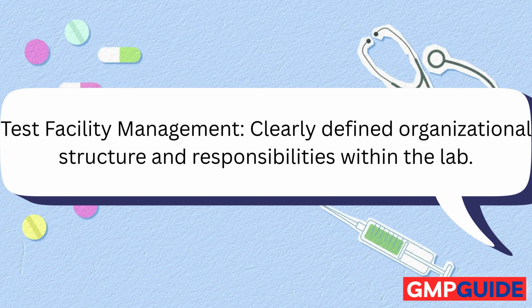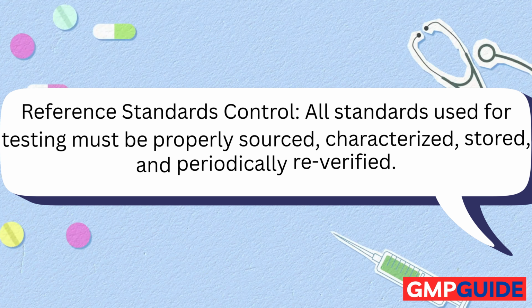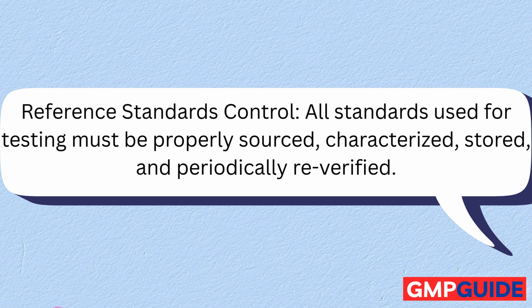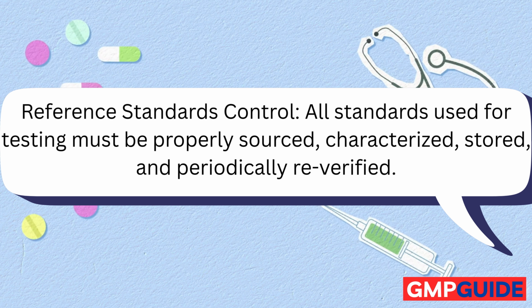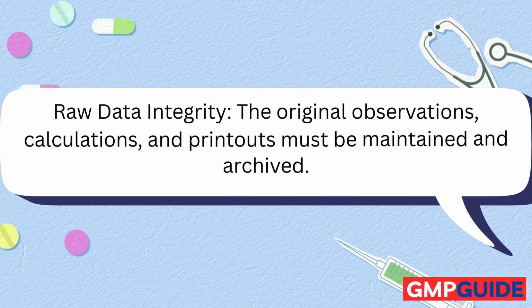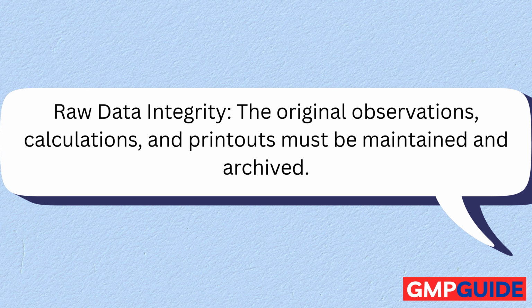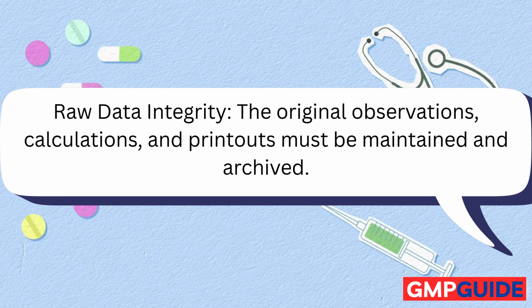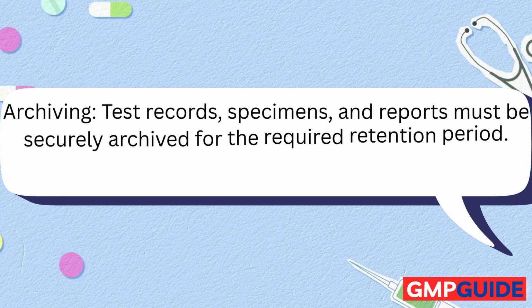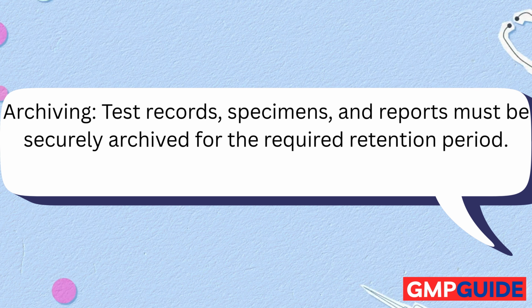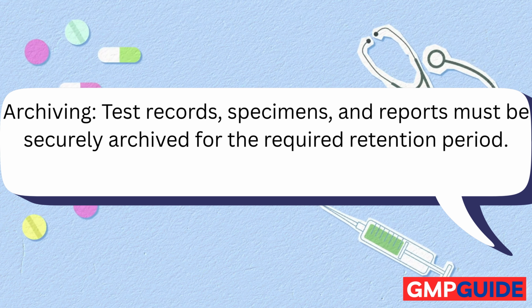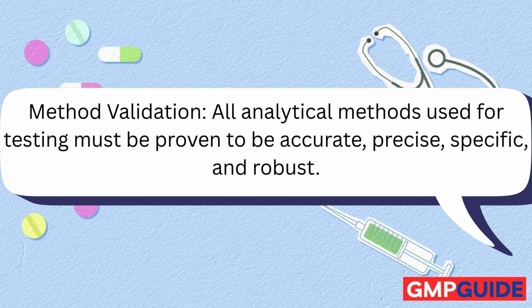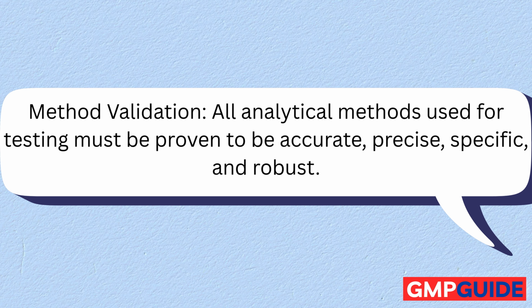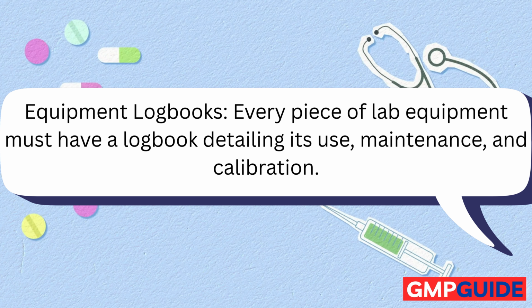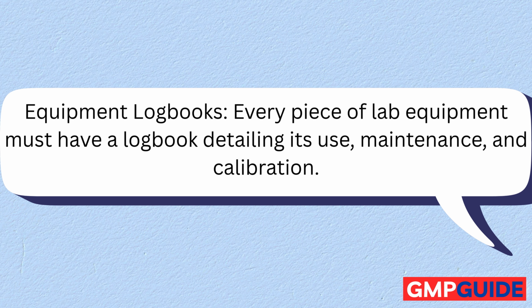Reference standards control. All standards used for testing must be properly sourced, characterized, stored, and periodically re-verified. Raw data integrity. The original observations, calculations, and printouts must be maintained and archived. Archiving. Test records, specimens, and reports must be securely archived for the required retention period. Method validation. All analytical methods used for testing must be proven to be accurate, precise, specific, and robust. Equipment logbooks. Every piece of lab equipment must have a logbook detailing its use, maintenance, and calibration.